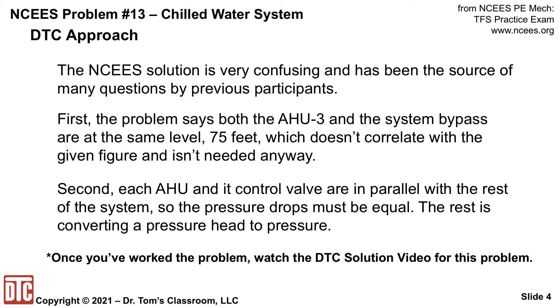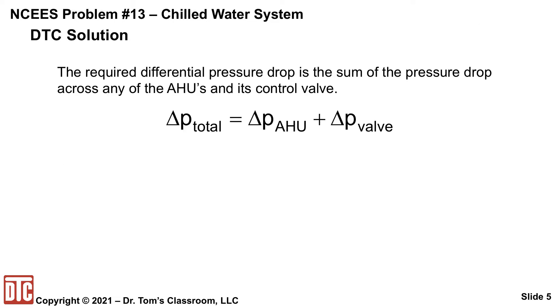Okay, let's see what we really need to do here. Well, the required differential pressure drop is the sum of the pressure drop across any of the AHUs and its control valve. So the total pressure drop is a combination of the pressure drop across the air handling unit plus the pressure drop across the valve, and we're given the valve is 5 psi.